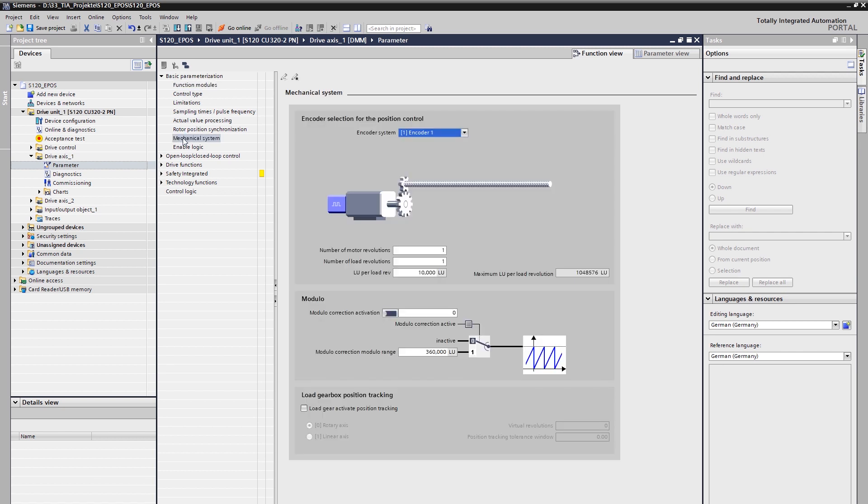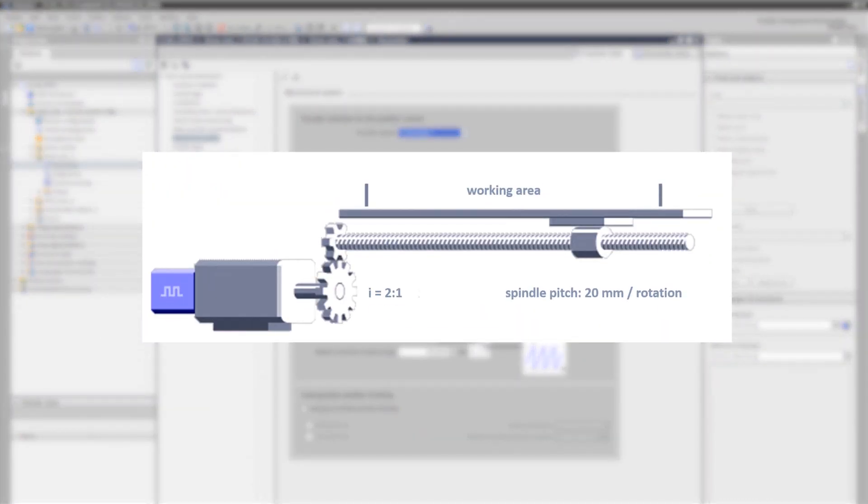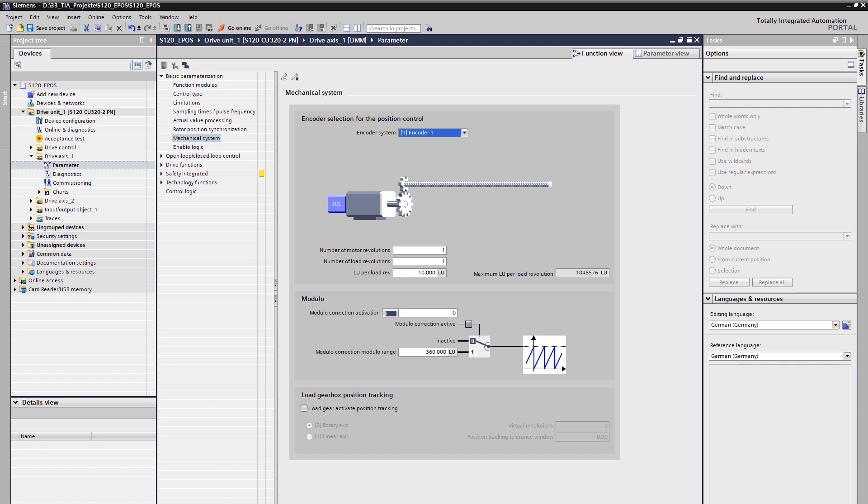Let's now have a closer look at our example mechanics. We are going to parameterize a linear axis. As you can see, we are operating a rotary motor that drives a linear axis by an attached spindle. There is a gearbox between the motor and the spindle with a ratio of motor side to load side of 2 to 1. The spindle pitch is defined to 20 mm of linear movement per one revolution of the load side. In this application, the motor encoder is used for position detection and the positioning should be realized with a resolution of 1 µm.